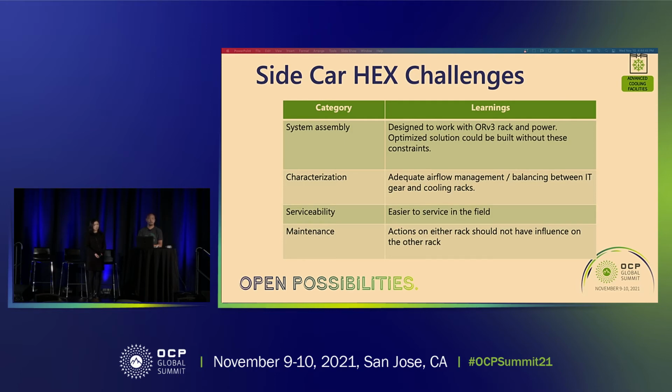So additional care must be taken to ensure that the peripheral components that aren't being cooled down by cold plates still receive enough cooling and enough airflow to properly cool them down.